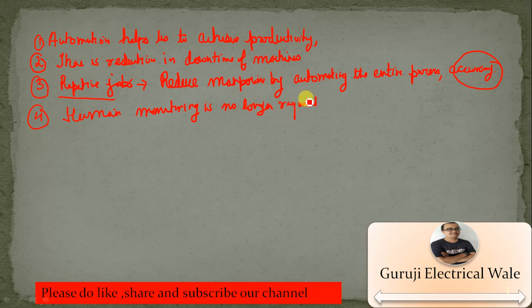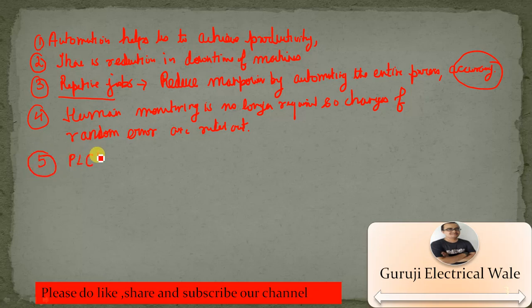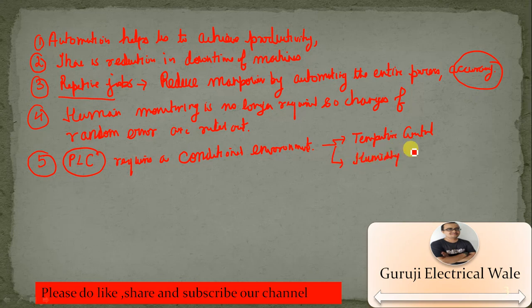So chances of random error, because random error can come in any system, are ruled out once you have installed the controller. Only thing is that a PLC requires a conditioned environment. Means you have to ensure wherever you are installing the device, it should have temperature control and humidity control. Otherwise, these two factors are the biggest enemy for this controller.